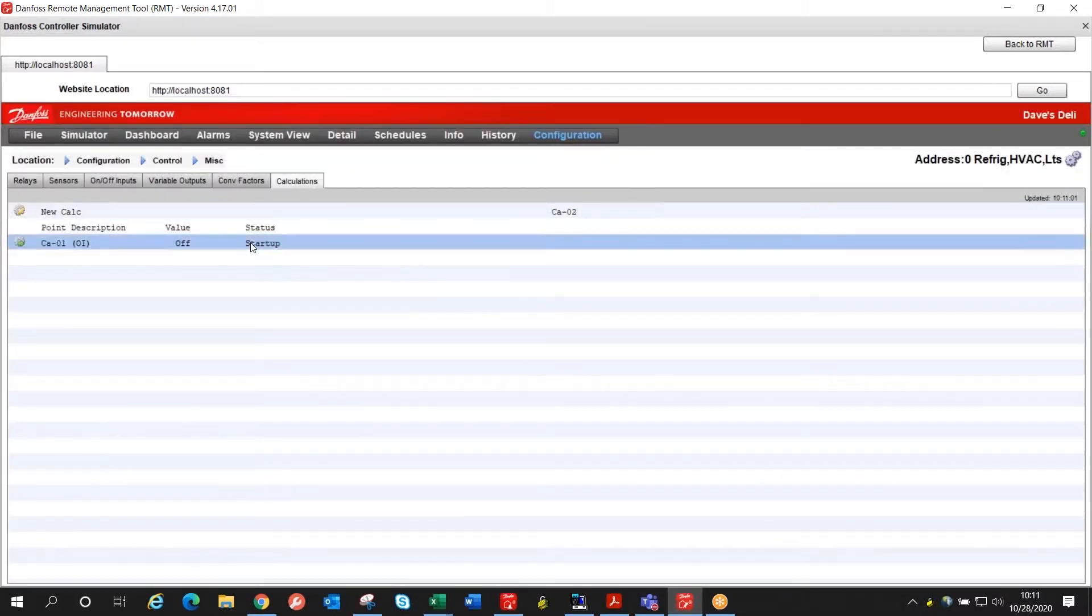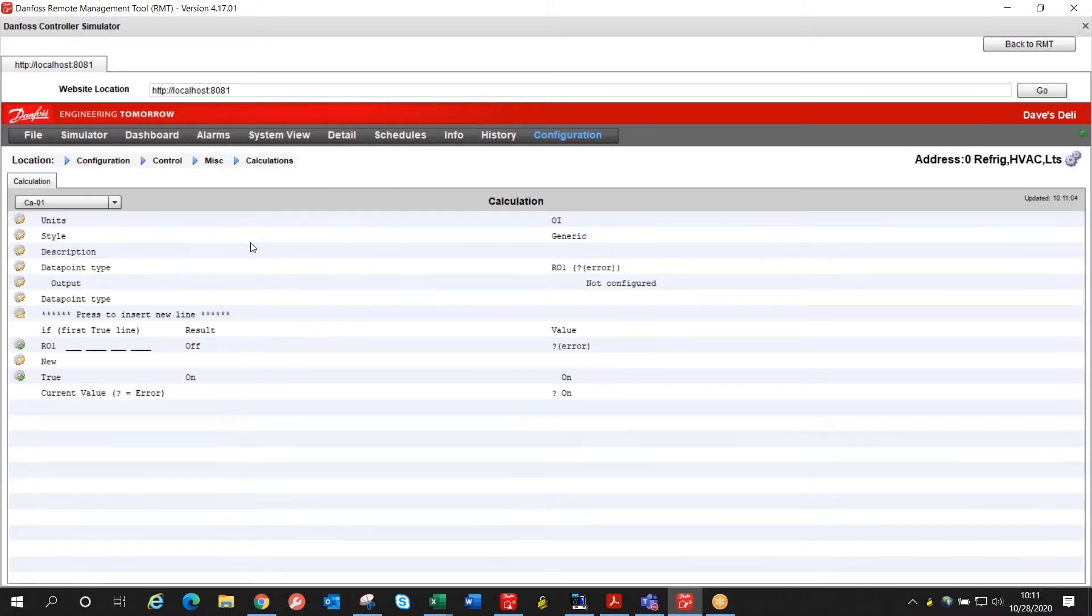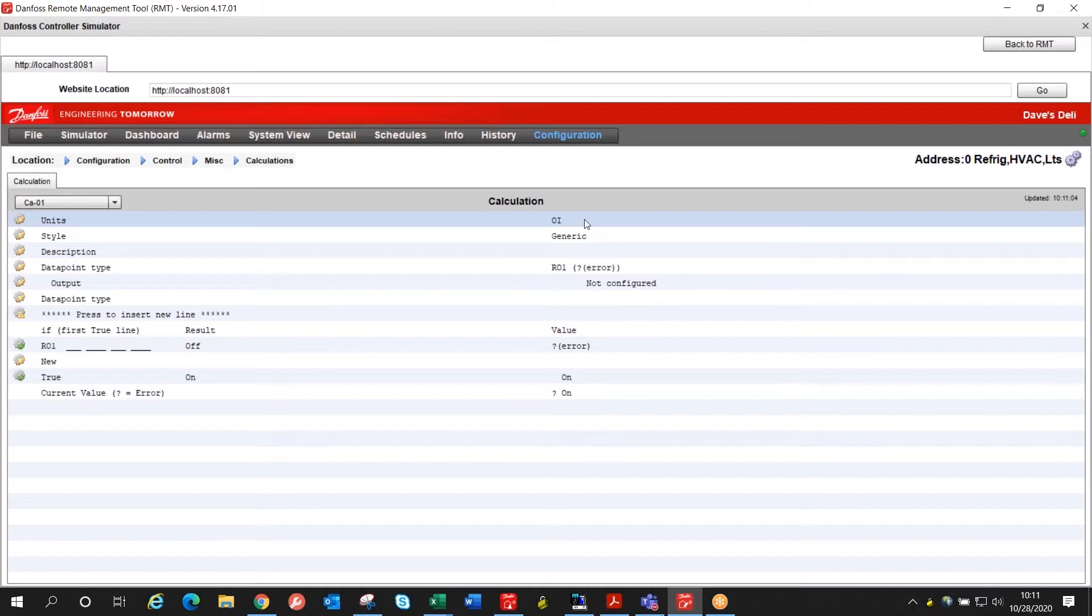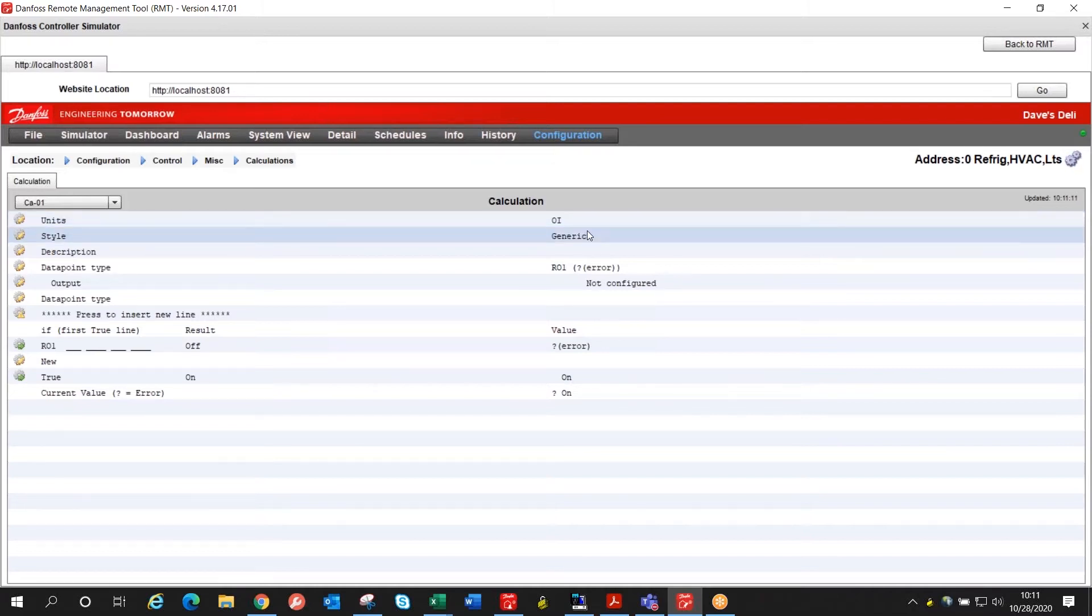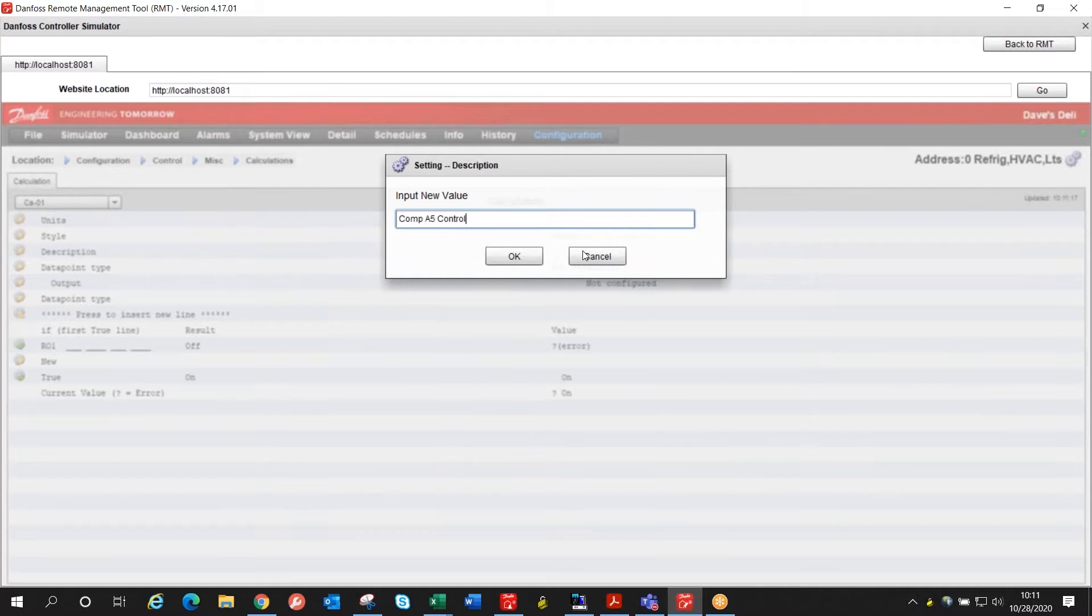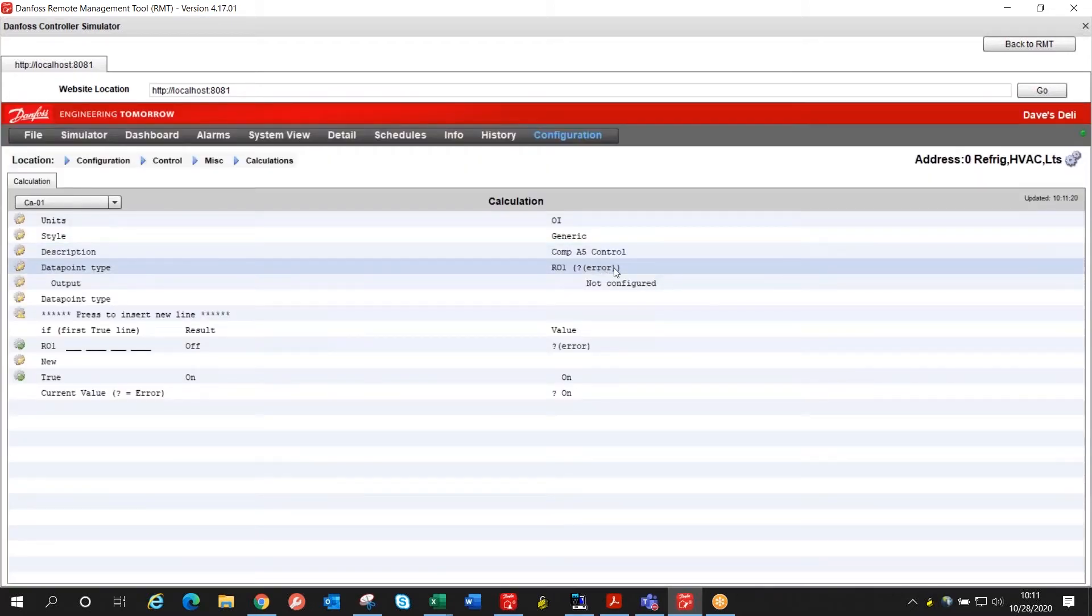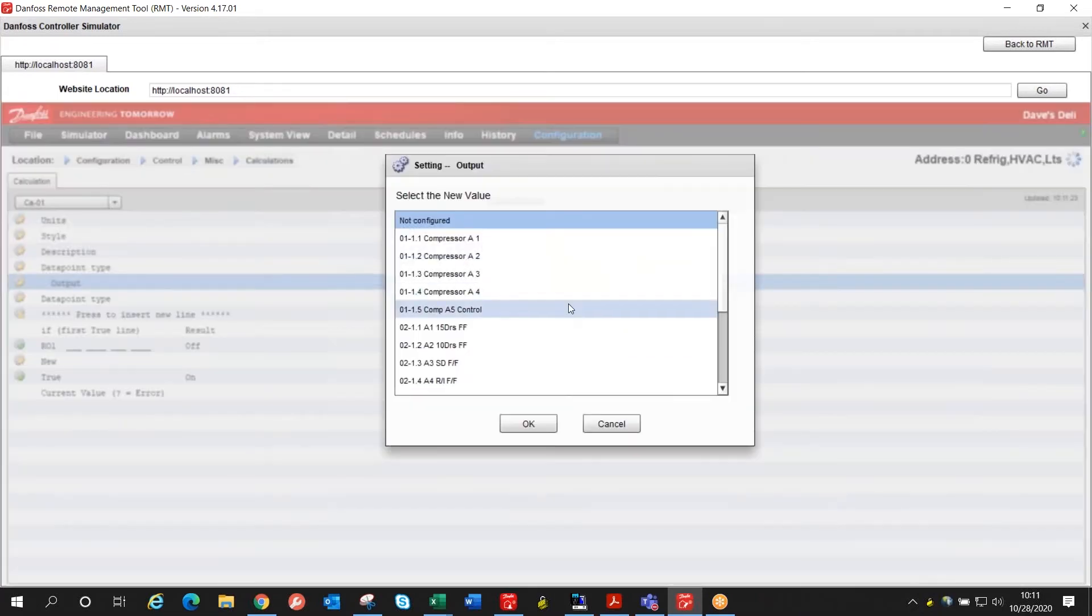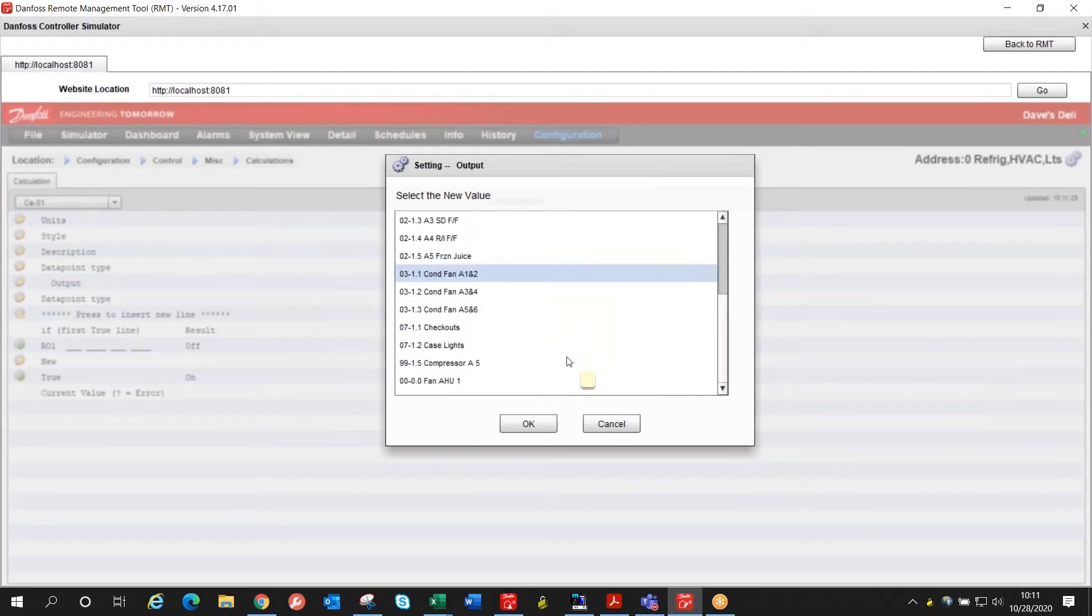This is our calculation, we'll double click it to edit it. It's going to be an on off calculation so OI is fine and generic is fine. Let's give it a name. My compressor I'm working on is compressor A5 so we'll give it a name and then the calculation already assigns a relay to start with so we're going to select the dummy relay that I've already assigned under the rack for that compressor.